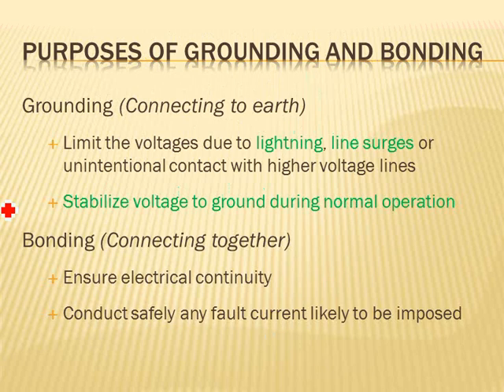So wherever you go in your plant, you're almost guaranteed to get 120, right? Plus or minus 5 or 10%. That's where stabilized voltage to ground during normal operation comes in. So wherever you go in your plant, the voltage between the hot and neutral is 120 plus or minus 5% fluctuation in load. And the voltage to ground on the 240/120 system, between the pipe and the hot, is 120. That's stabilizing the voltage to the ground.